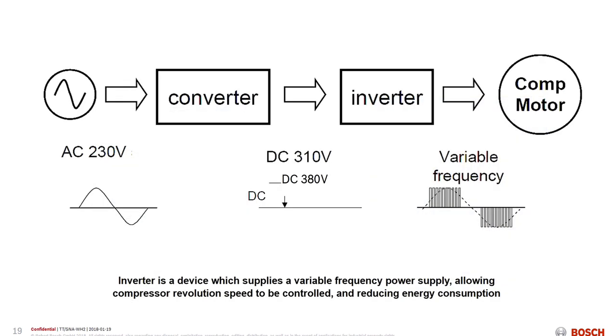Here's how we work. 230 volts, basically AC current, is going to come into the condensing unit. I'm going to take that and convert it to DC voltage. At that point, I'm going to invert the DC voltage to allow my compressor to see an AC 3-phase voltage, so that I can manipulate, modulate my compressor, always starting at the lowest denominator and changing accordingly to the comfort demands of the sensor.